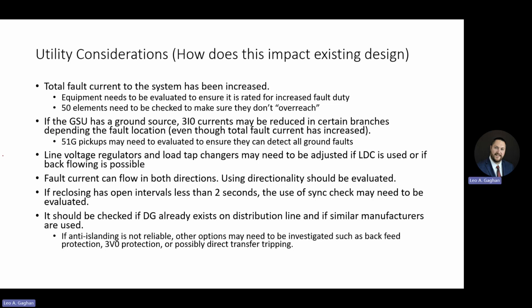So some other things we haven't talked a lot about, but line voltage regulators and load tap changers may need to be adjusted if line drop compensation is used, or if backflow is possible. I don't want to get too deep into that. Fault current can now flow in both directions. It should be evaluated if we want to use directionality. Can't use negative sequence directional elements very reliably, so we'd want to look at a zero sequence polarized, or we may just want to bump the negative sequence pickups above what the inverter can put out. And if reclosing has open intervals less than 2 seconds, use of sync check may need to be evaluated.